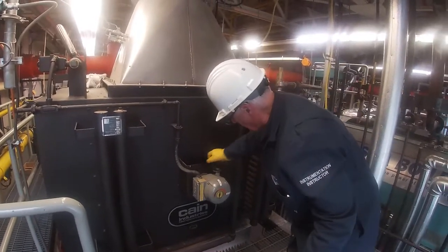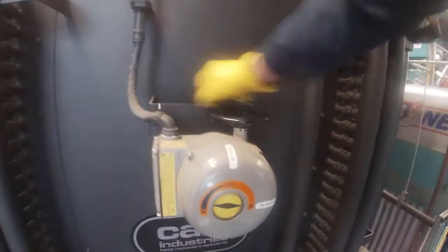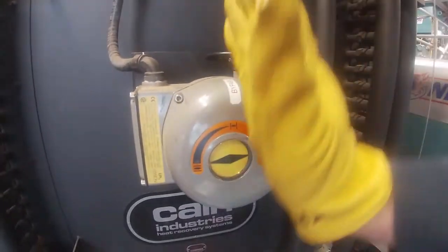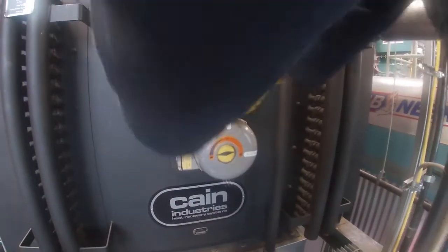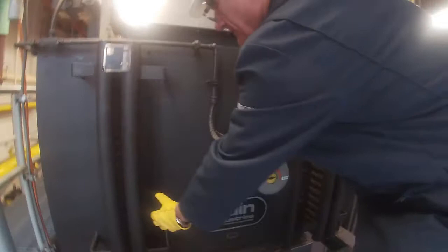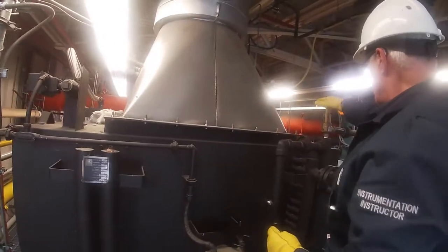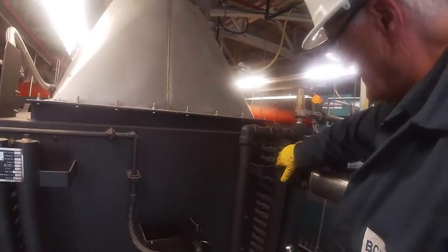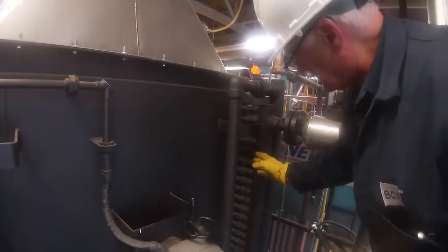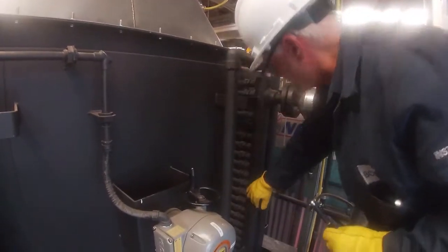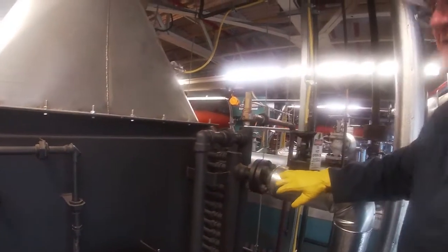If I take this economizer and put it into operate mode, what I've just done is I've taken a damper and I've moved it to that position, which now means that the gases are being forced out, up through these tubes, goes around the back, comes over the other side, comes out on these tubes, which comes out on the top side, and comes out on these tubes, and then gets forced through this bank of tubes on here, and then finally comes out of here as hot water.